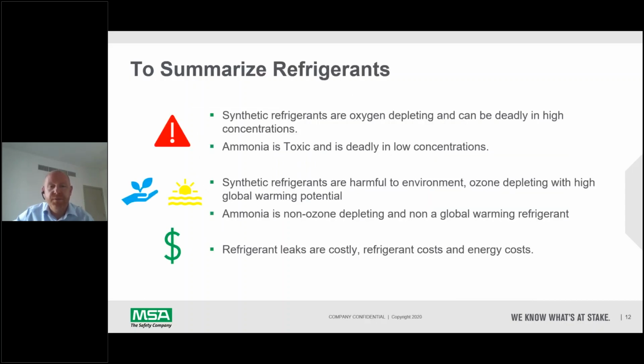Just to summarize about refrigerants then, they're synthetic gases and they're oxygen depleting, so they can be deadly in high concentration. If you're breathing in a refrigeration gas, you're not breathing in oxygen. Ammonia can be toxic and deadly in low concentrations, and we'll review that a little bit later. They're harmful to the environment and can be ozone depleting with high global warming potential, but things are changing now with all these new agreements being signed. And refrigerant leaks can be costly. So you have the refrigerant costs and then the increase in energy costs for the owner of the plant.